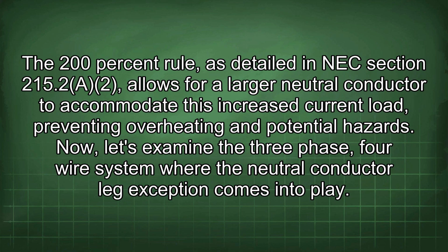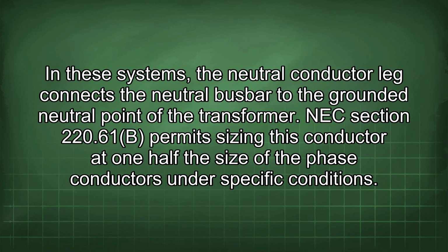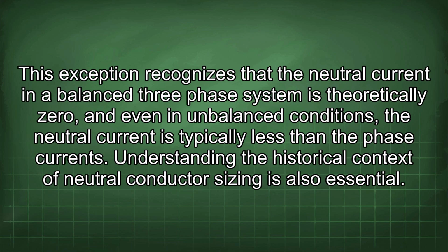Now let's examine the three-phase, four-wire system where the neutral conductor leg exception comes into play. In these systems, the neutral conductor leg connects the neutral busbar to the grounded neutral point of the transformer. NEC section 220.61(B) permits sizing this conductor at 1/2 the size of the phase conductors under specific conditions. This exception recognizes that the neutral current in a balanced three-phase system is theoretically zero, and even in unbalanced conditions, the neutral current is typically less than the phase currents.